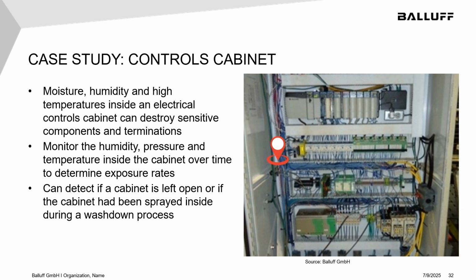Controls cabinet. This is a little bit of an unusual one. We have several customers in the food and beverage business. They have to wash down their whole area multiple times a day and have had problems where the control cabinet wasn't quite locked and closed, and they had ingress of the hot cleaning fluid into that area and destroyed electrical equipment. They have a temperature and humidity sensor in there that detects the increase in humidity and temperature if the door is cracked open, and sends an alert and alarm that tells the operator to stop the cleaning process because the door is cracked, and avoids destroying the electrical equipment in the cabinet.